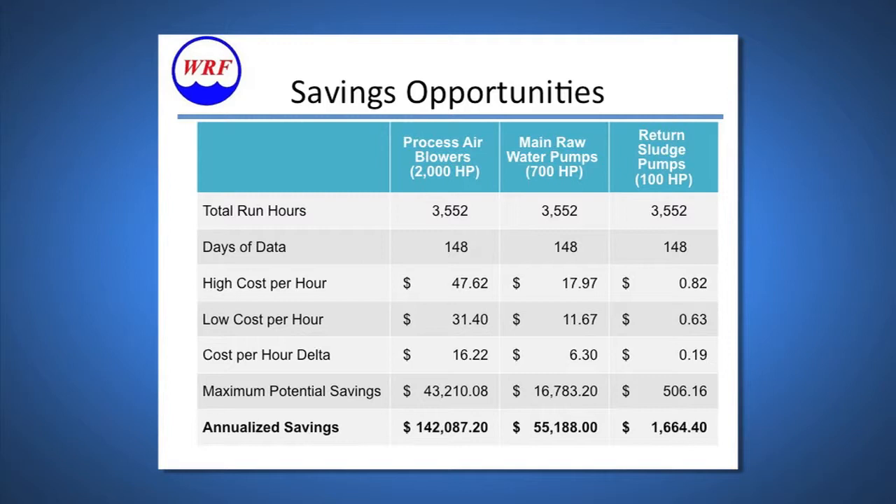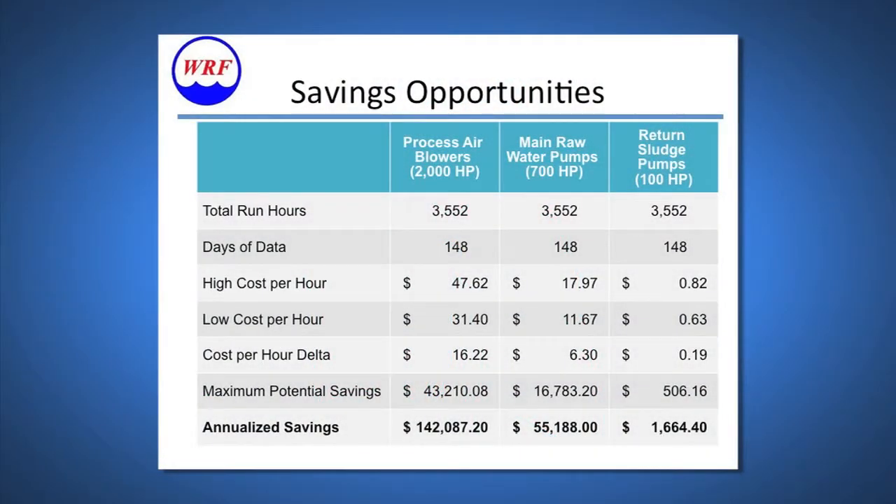We went with three different systems: our 2,000 horsepower process air blowers, our 700 horsepower main raw water pumps, and our 100 horsepower return sludge pumps. We wanted to see what difference in savings could be attained by using this program. The cost delta between our highest and lowest cost-per-hour to operate an asset was $16.22; the next was $6.30. This still led to an annual savings of close to $200,000 for our facility.